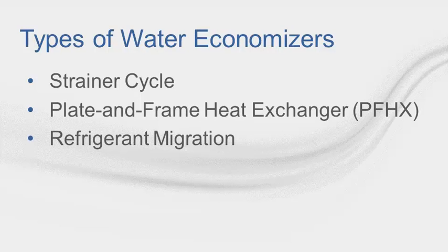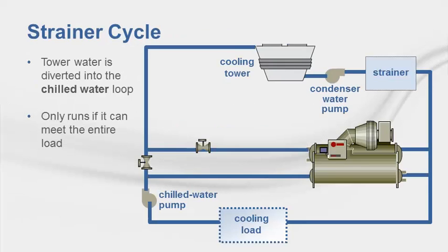Three types of water economizers are considered within this presentation: strainer cycle, plate and frame heat exchangers, and refrigerant migration. In the strainer cycle, tower water is valved directly into the chilled water loop when the outdoor air wet bulb is low enough. It's the most efficient water economizer option, but is not widely accepted due to fouling concerns.